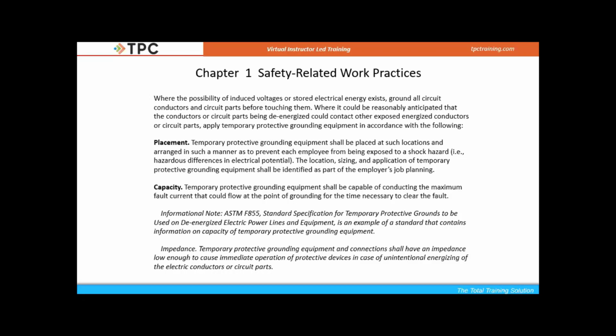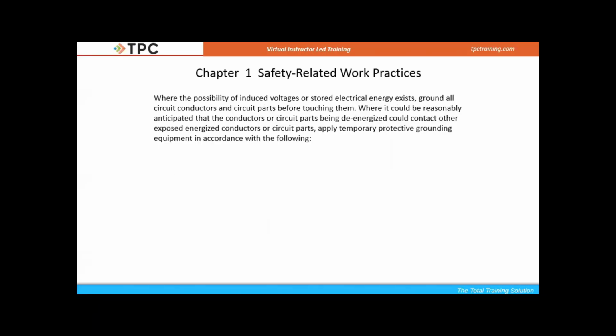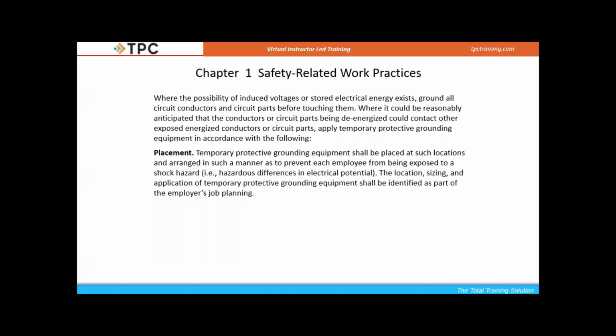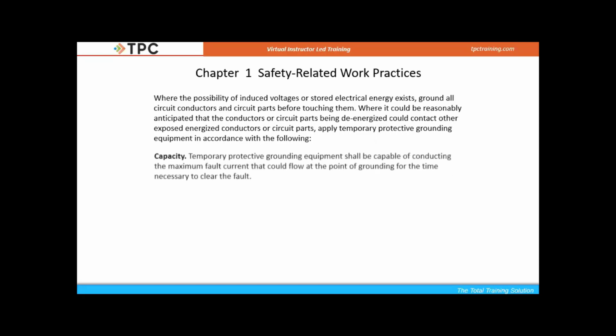And it is going to make sure that if something does become re-energized that is out of our control, hopefully we're going to open up an overcurrent device because we do have that circuit grounded. This is all going to happen if we do have that possibility of induction or capacitance re-energizing our circuit, which happens a lot above 1,000 volts. And we're going to place them in the proper placement. I'm going to give you an idea when I pull up the picture of how we do it.